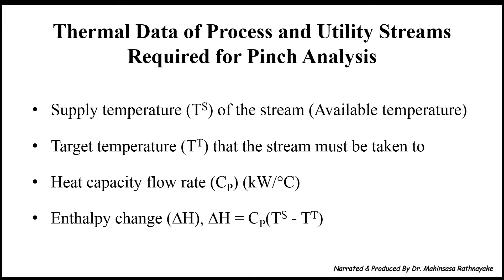We need to extract thermal data of process and utility streams for pinch analysis using the process flow diagram. There are four types of thermal data required: supply temperature of the stream, meaning the available temperature; target temperature that the stream must be taken into; heat capacity flow rate of the stream in kilowatt per degree Celsius; and enthalpy change for that stream. Enthalpy change can be calculated using the heat capacity flow rate and the difference between the supply temperature and the target temperature.